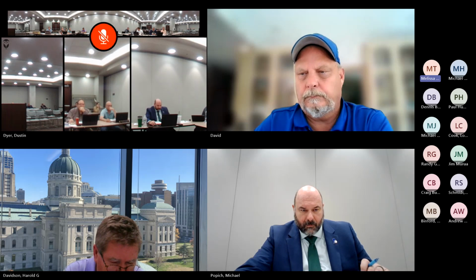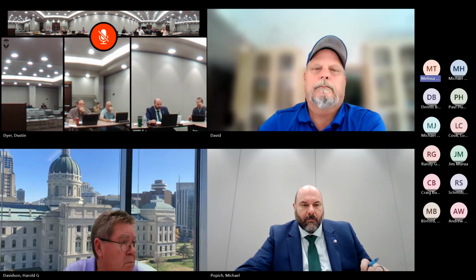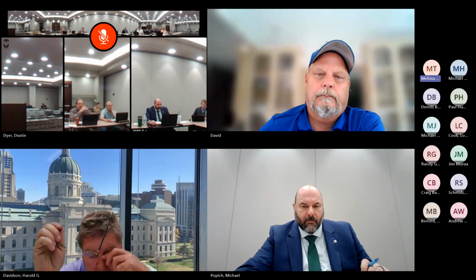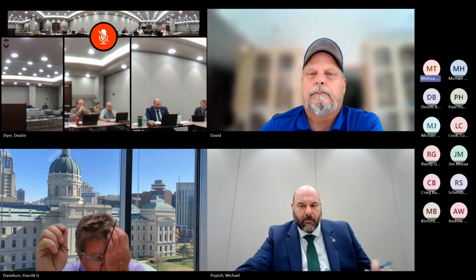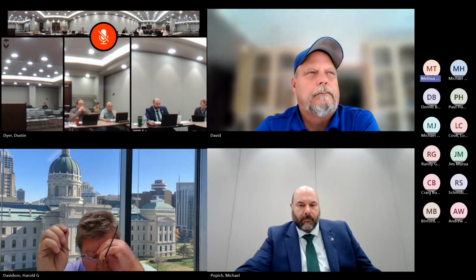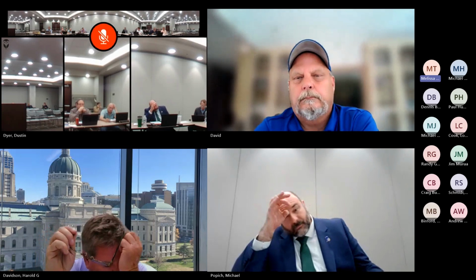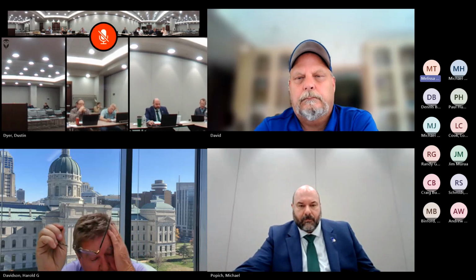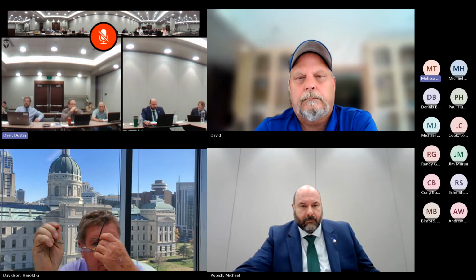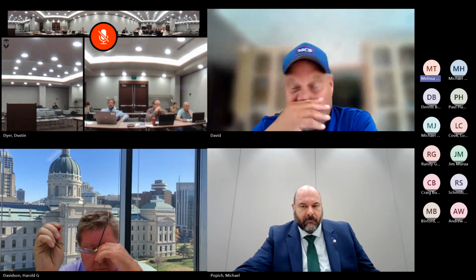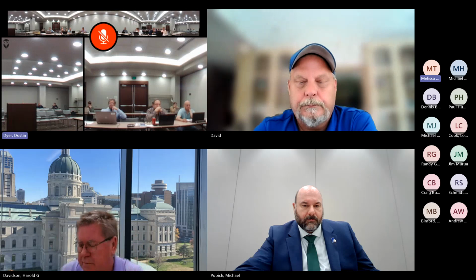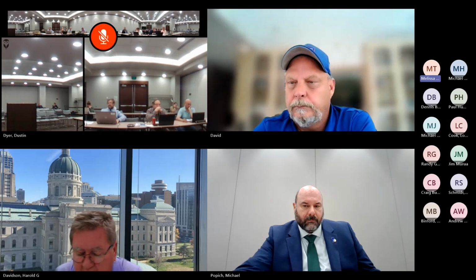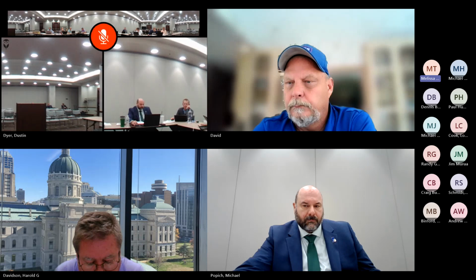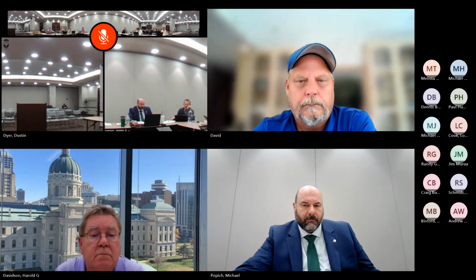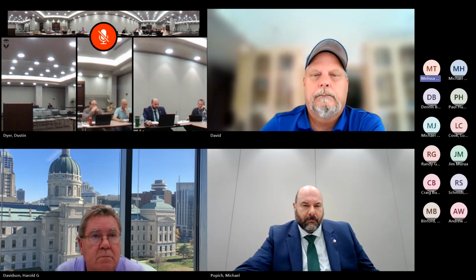They will be requesting to not sprinkler the building. They will be installing a new fire alarm and connected smoke detection system throughout the existing sanctuary building. Currently, the building has neither. Both the lower level and the first floor sanctuary exit to grade. The lower level is classroom, pretty much all sanctuary space. There are 5 exits provided from the sanctuary, and our maximum travel distance in the sanctuary is 80 feet. Code would permit 200.